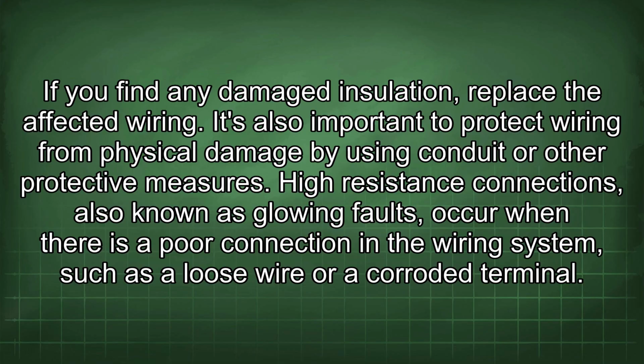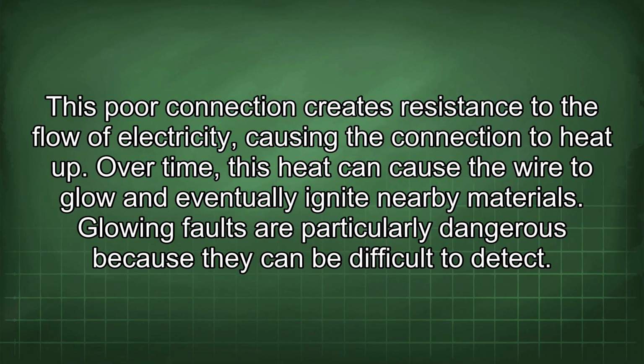High resistance connections, also known as glowing faults, occur when there is a poor connection in the wiring system, such as a loose wire or a corroded terminal. This poor connection creates resistance to the flow of electricity, causing the connection to heat up. Over time, this heat can cause the wire to glow and eventually ignite nearby materials.